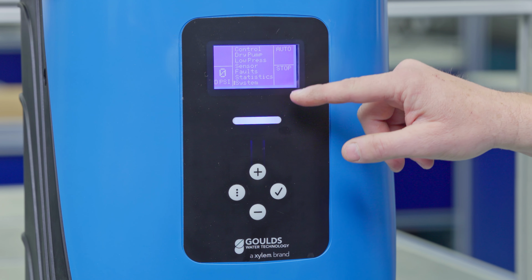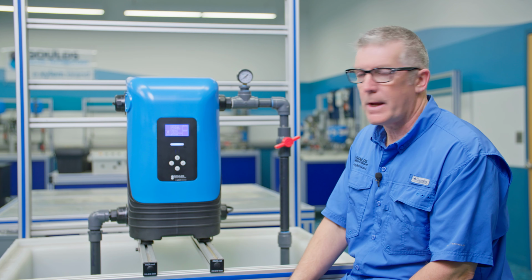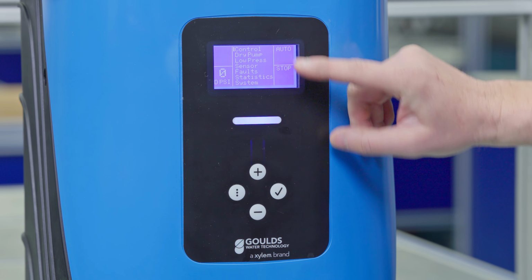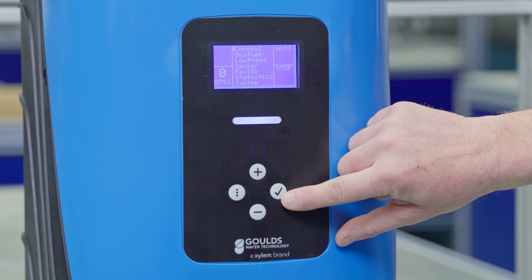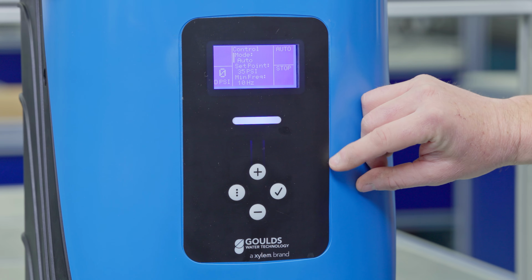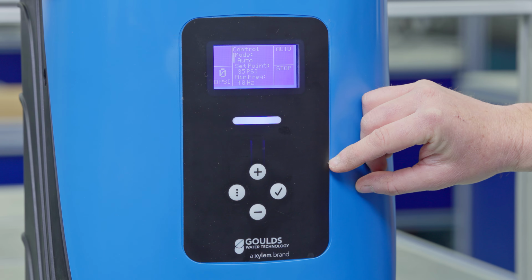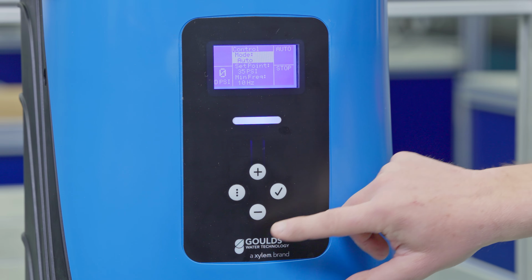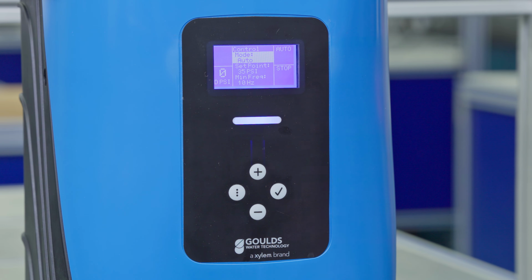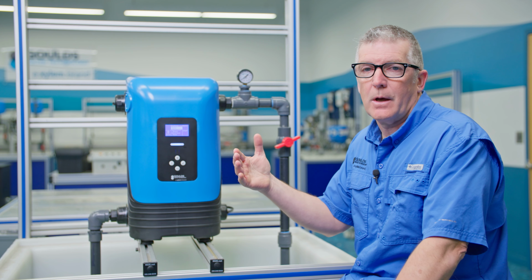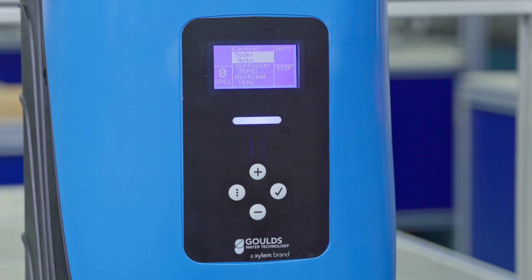And we're going to go through each and every one of these parameters. So we'll get to the top one here, which is control. So what you want to do is hit the enter button, and you can see we're in the mode. Again, hit the enter button to highlight it, and then you can hit your up and down button to see what options you have. So we can see the default here is auto. That just means that it's running off of the pressure sensor, the transducer.